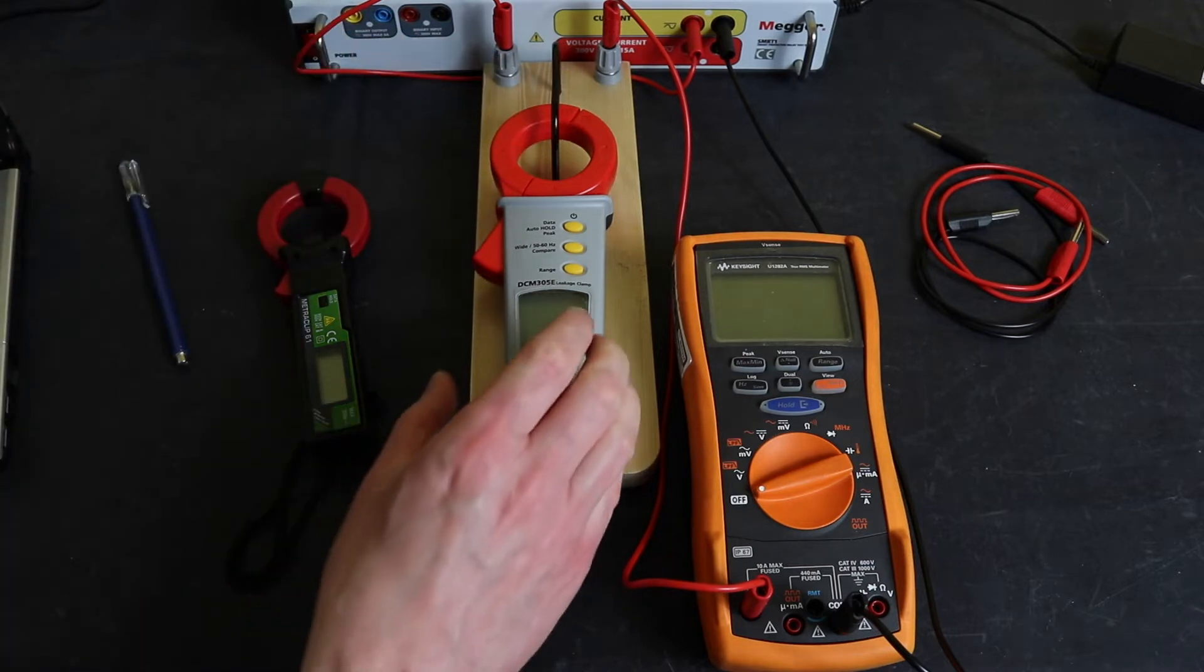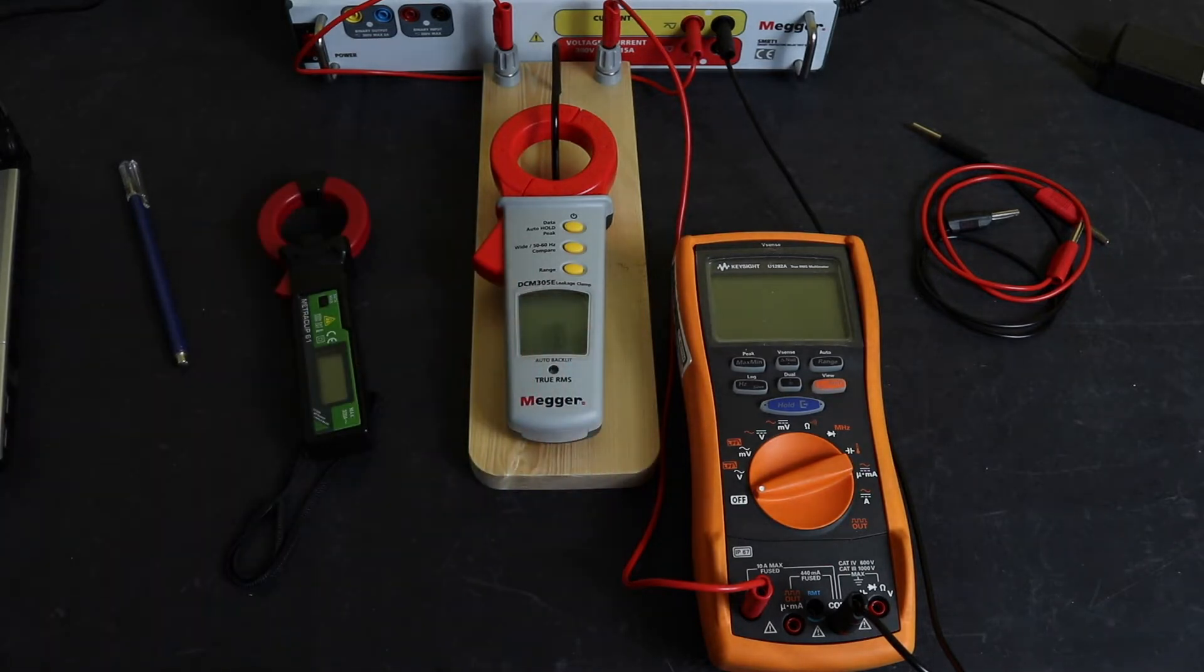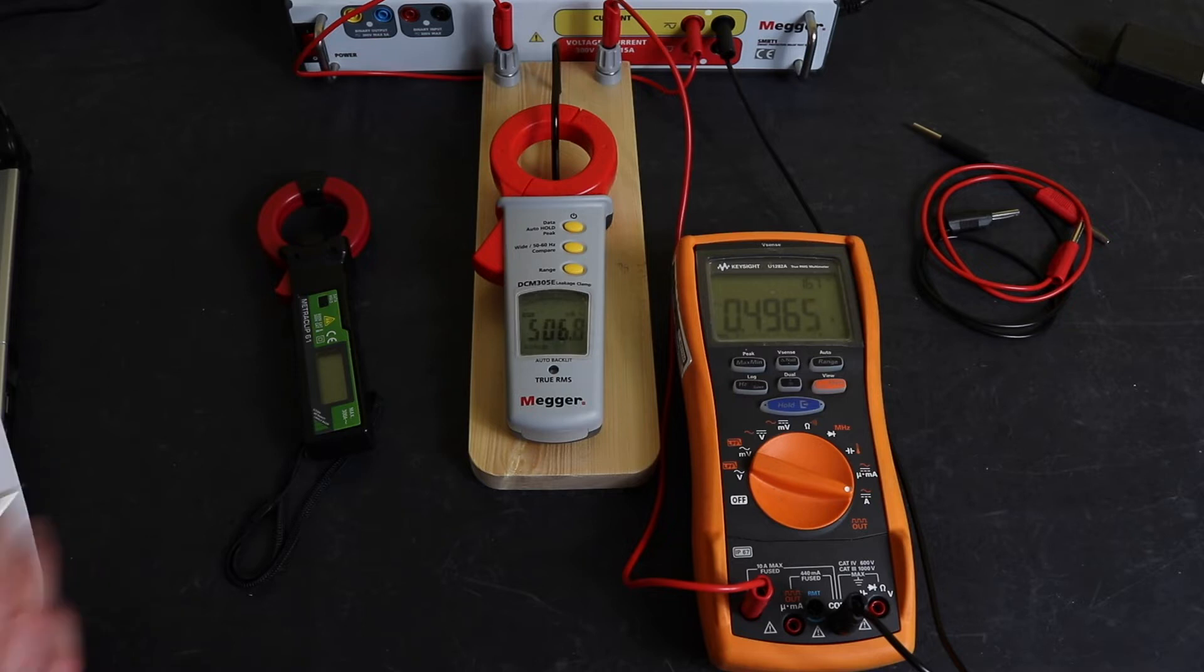Okay, so we're running on 500 milliamps here on the Megger. This is the instrument that was a little bit stroppy. 506.7 against 496.5, which is probably even worse because I did the original one at 500 milliamps.